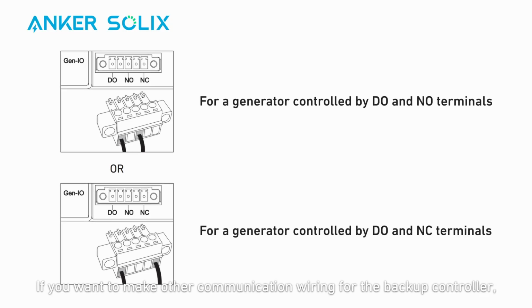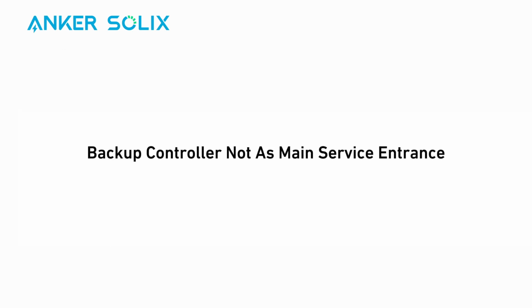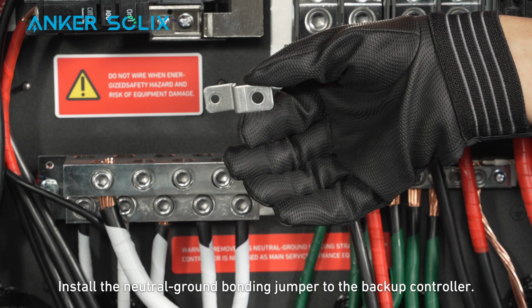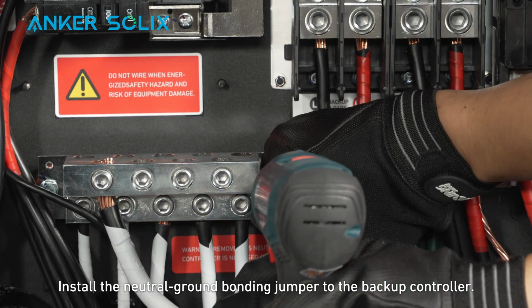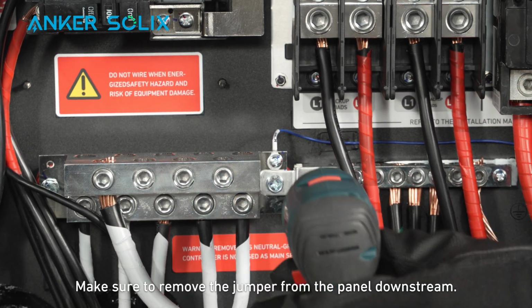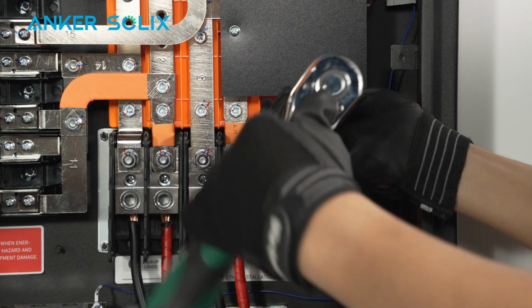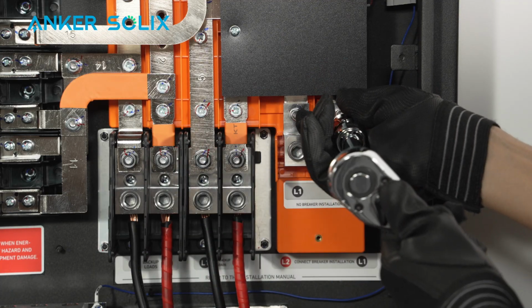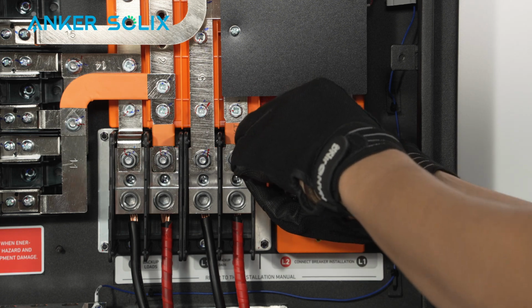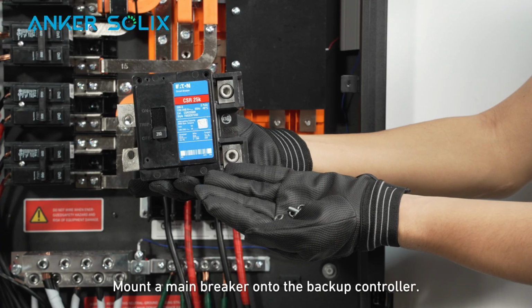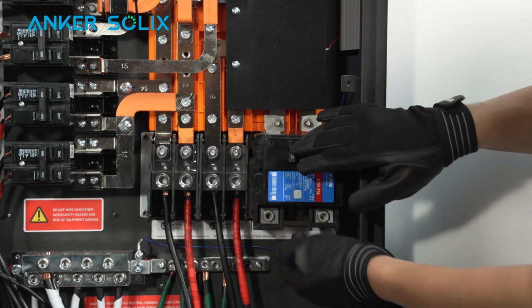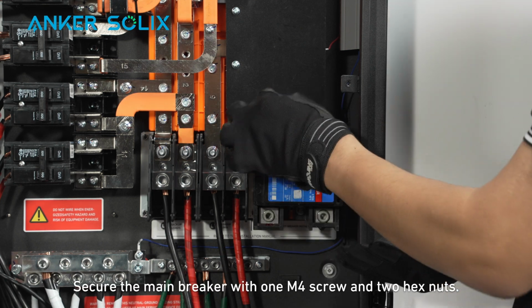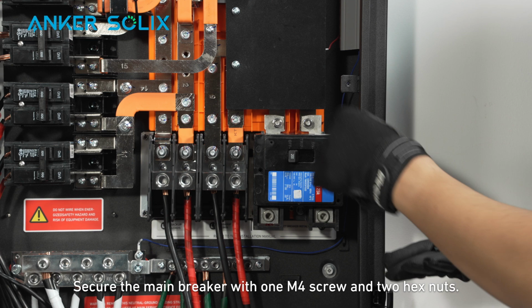If you want to make other communication wiring for the backup controller, you need to insert the signal cables into an appropriate terminal block connector and plug it into the terminal block socket. Install the neutral ground bonding jumper to the backup controller. Make sure to remove the jumper from the panel downstream. Mount a main breaker onto the backup controller. Secure the main breaker with one M4 screw and 2 hex nuts.